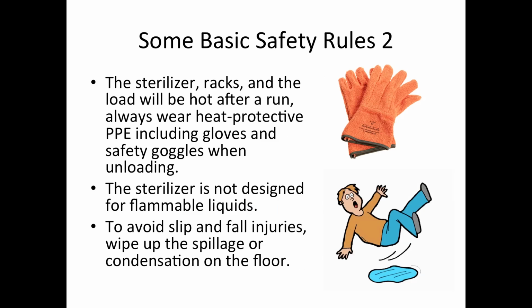To continue on some basic safety rules that apply again to all autoclaves, remember that the sterilizer, the racks, and the load will be hot after a run, so you're going to wear heat-protective personal protective equipment, primarily heat-resistant gloves, but it is also necessary to wear safety glasses or safety goggles when unloading the autoclave in case there are any splashes or spills or hot liquid coming out. Another thing to remember is that the sterilizer is not designed for flammable liquids, so keep the flammable liquids out of it. And to avoid any kind of slip and fall injuries, the floor in front of the autoclave has to be kept dry. We are dealing with steam, and if the steam escapes and condenses, it can form a puddle on the floor.